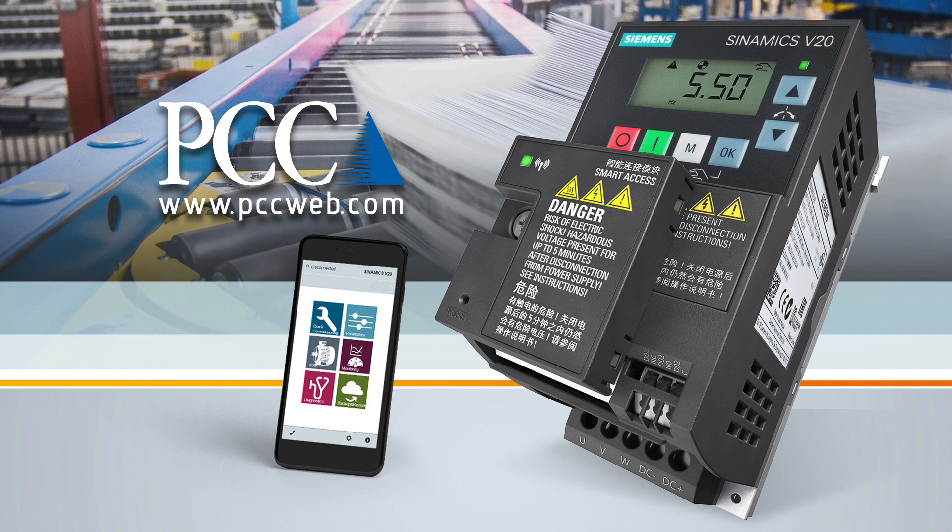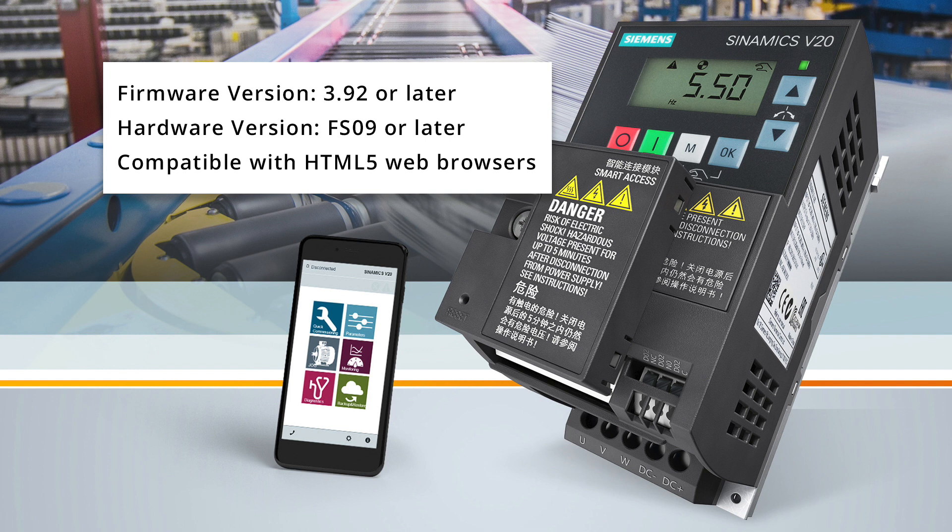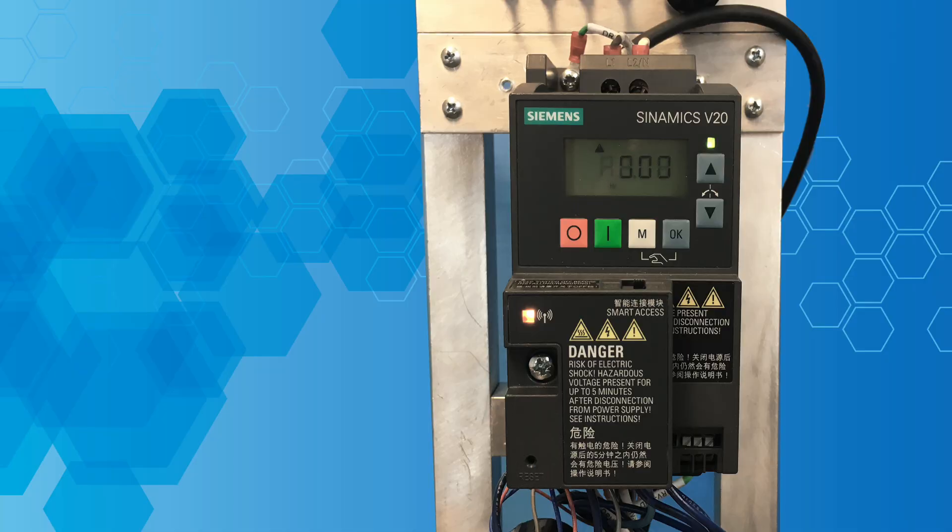To use the Smart Access Module, your drive must be firmware version 3.92 or later and hardware version FS09 or later. The Smart Access Module works with HTML5 compatible web browsers and to use it you plug it onto the front of your V20 drive.